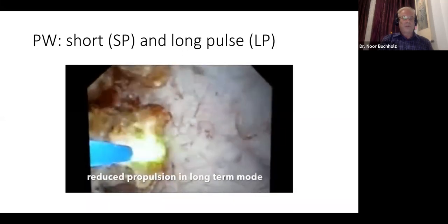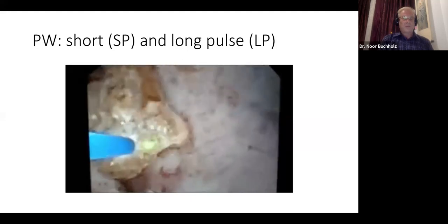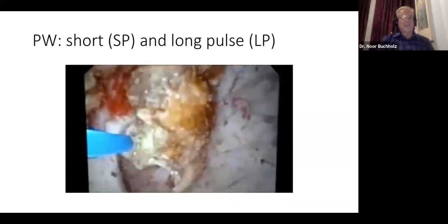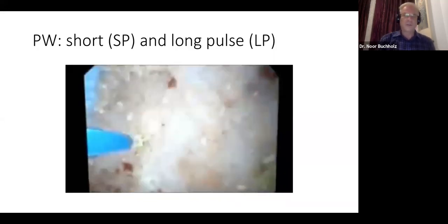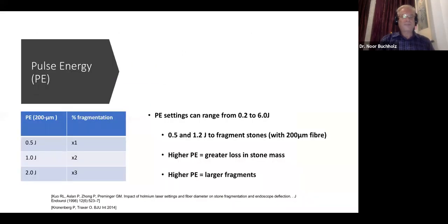Now, for the big fragments, we are back into long pulse mode. So they stay in place. So this illustrates nicely the effect of long and short pulse in the laser. Now, let's come to the next one, which is the pulse energy.